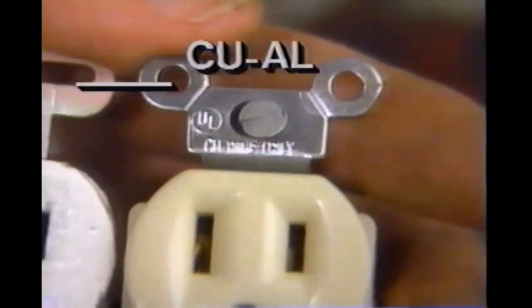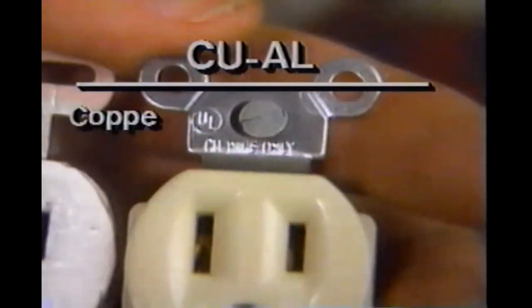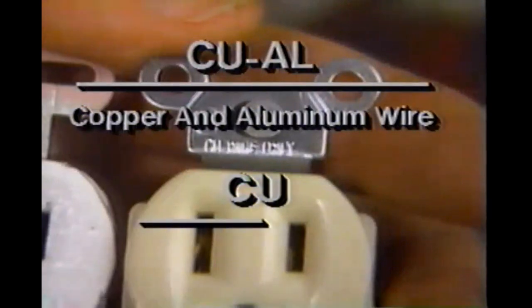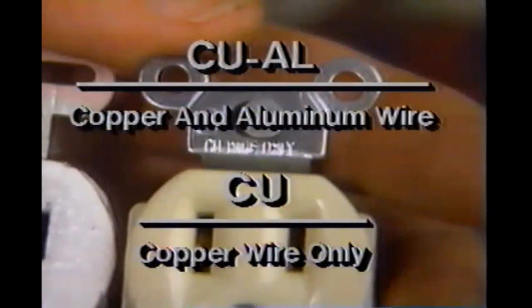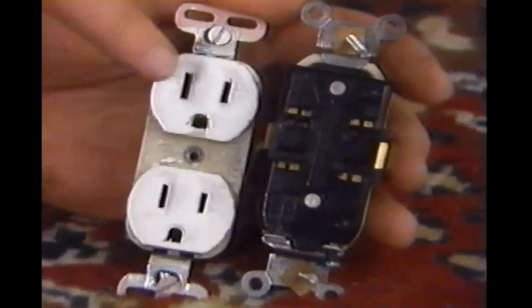Receptacles marked with CUAL can be used with either copper or aluminum wire. Receptacles marked with CU, or those unmarked, may be used with copper wire only. Determine which you need before buying your replacement. We recommend that you use back-wired receptacles because they're easy to install. Merely measure and strip the wires and insert the stripped wire ends into the terminal holes.